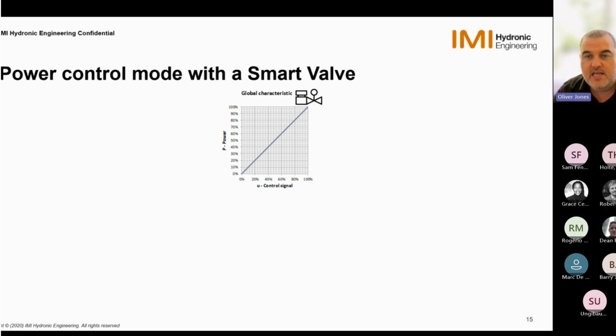So we get the power P that is linear with the control signal out of the controller U. So this is the dream of control theorists. A perfect line is what you need if you want very good control or a very good control system. But this is hiding a lot of what's happening inside the black box with the sub-control loop inside the smart valve. So the net result looks perfect.